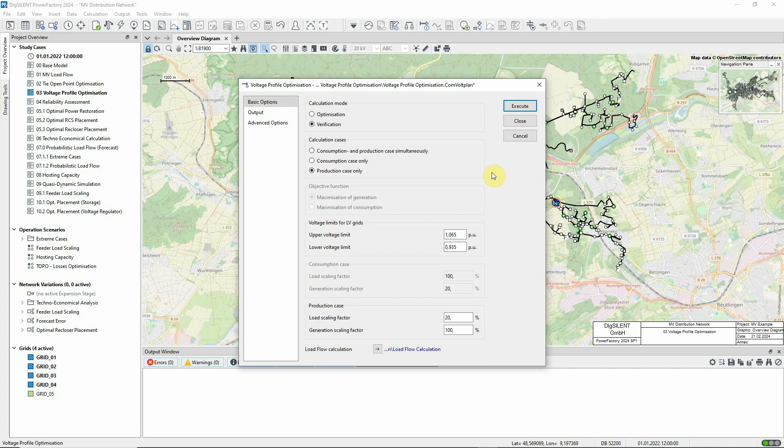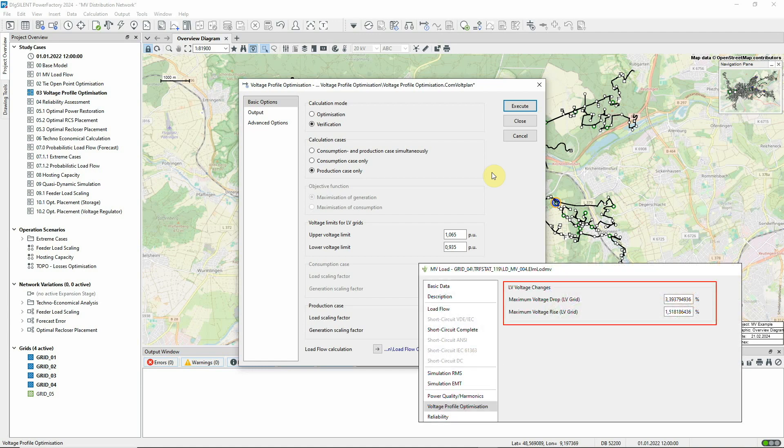In this case, we'd expect high voltages rather than low voltages to be the problem. The MV load elements actually represent LV grids, and these parameters in the load elements are used for modeling the maximum voltage drop and rise within the LV grids with respect to the transformer LV side voltage.